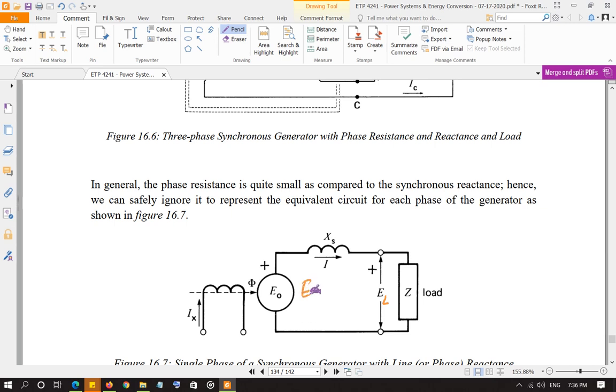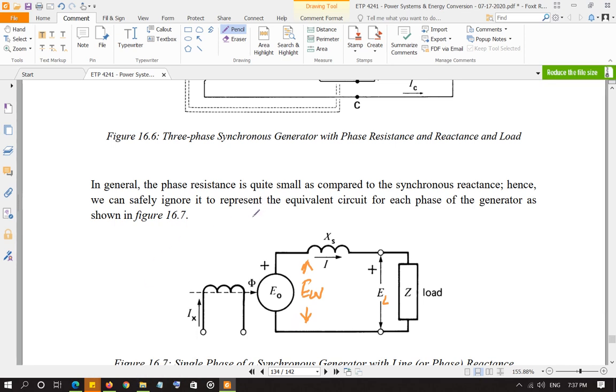The per-phase circuit shows the phase voltage line-to-neutral E-naught, the synchronous reactance, and the load connected with load voltage E_L. This is line-to-neutral phase voltage, not line-to-line, because the synchronous generator stator is connected in Y. If the load is connected in Y, use line-to-neutral voltage; if connected in delta, the load voltage is line-to-line. The synchronous reactance X_s is the reactance of the coil in which voltage is induced in each phase, and it must be determined before calculating load current.